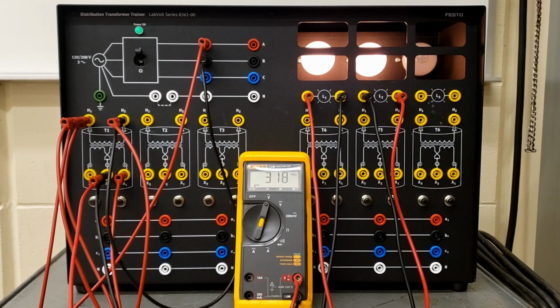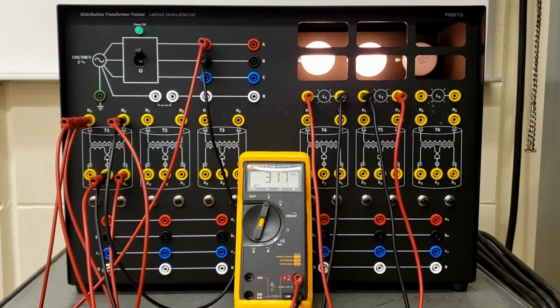We need to work on the write-up in that we should be taking a voltage reading first, then connecting up the bulbs across that load, because we don't want them to put 328 volts across the lamp, which is only good for 230 volts. So you can see here that you really want to go through this nice and slowly with the students, going through a full lesson with them prior to them sitting at the actual station.